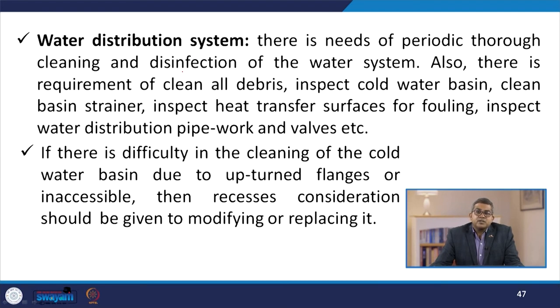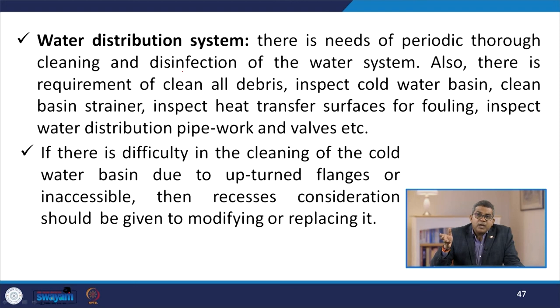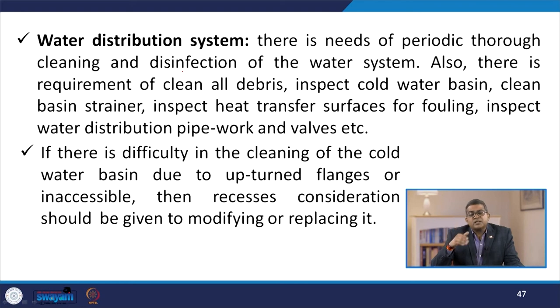Water distribution system: there is a need for periodic thorough cleaning and disinfection of the water system. Requirements include cleaning all debris, inspecting the cold water basin, cleaning the basin strainer, inspecting heat transfer surfaces for fouling, and inspecting water distribution pipework and valves. If there is difficulty in cleaning the cold water basin — sometimes due to upturned flanges or inaccessibility — consideration should be given to modifying or replacing it.